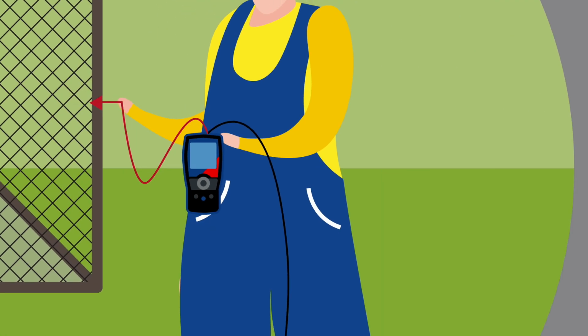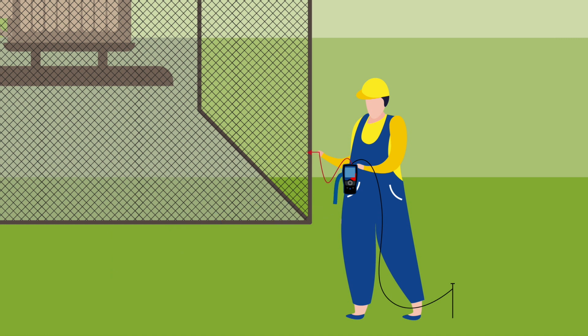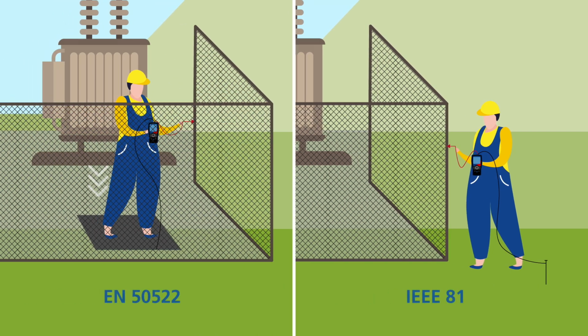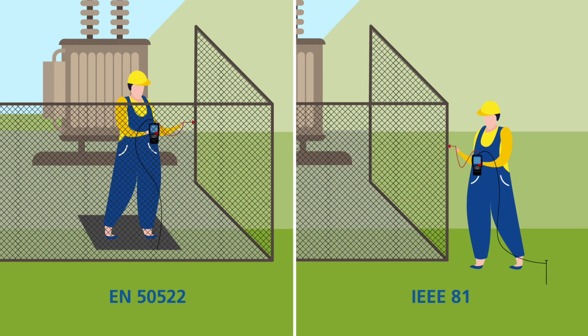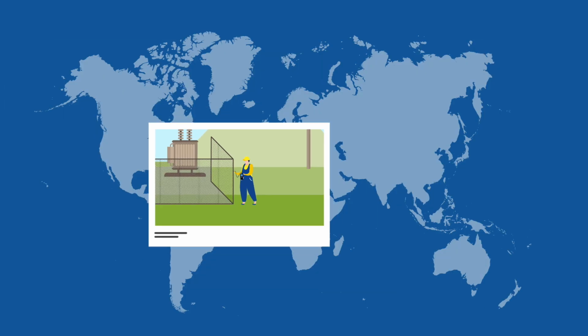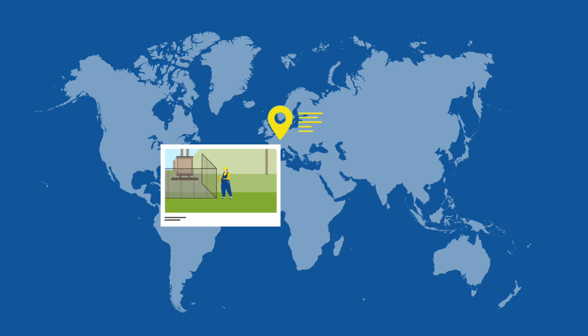With our handheld measuring device HGT1, resulting voltages of injection can easily be measured and recorded. It offers a wide dynamic frequency range in combination with high sensitivity. This allows users to measure very small voltages and reliably distinguish them from interference and disturbances. The switchable input resistors of the HGT1 are compliant with the IEC and IEEE step and touch voltage measurements. On top of that, measurement points can be combined with pictures or maps, including GPS locations, to obtain appropriate documentation. This helps with reporting and recurring measurements in the future.